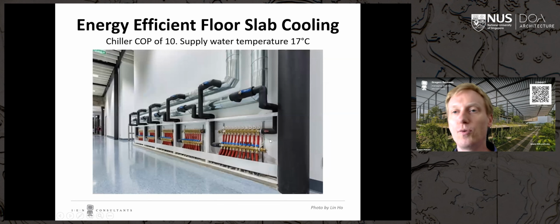This is how the floor slab cooling system looks in reality: pipes that go into the concrete slab, take some loops, and after about 100 meters come back, because beyond 100 meters the pressure drop becomes too high. The water goes in at about 17 degrees and comes back at about 19 degrees, giving off cooling so the floor surface is about 20 to 21 degrees. This is also high temperature cooling, just like in the ST Diamond building shown earlier, which let us get a chiller COP of 10 — quite high efficiency.